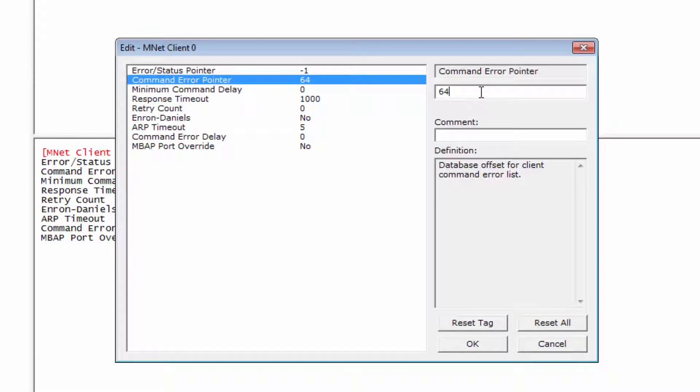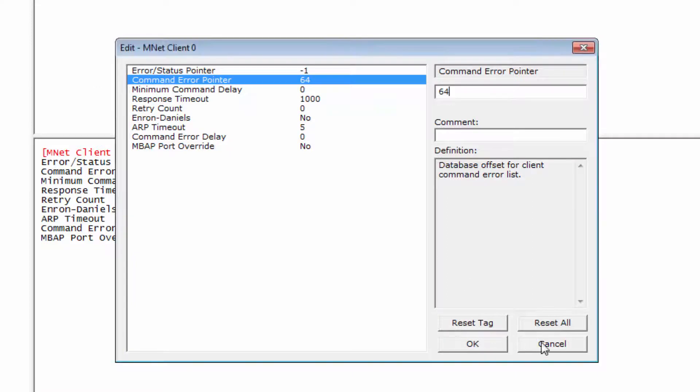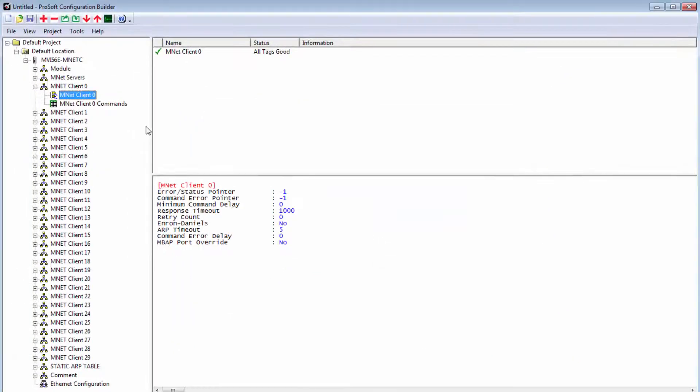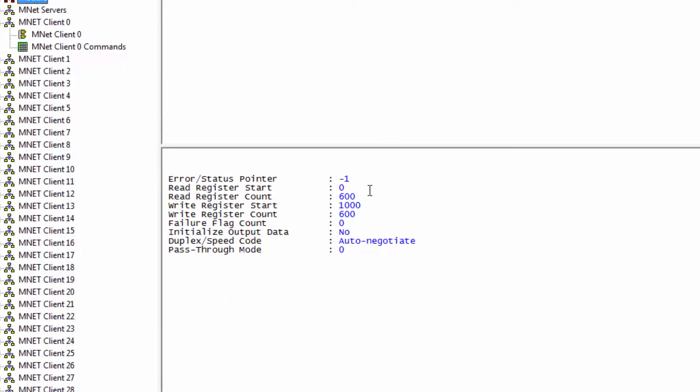Also, if you want the error code data to be accessible by the program, it must be placed within the Read Data section of your module. We recommend setting the Command Error Pointer towards the end of your Read Data section. So if I take a look at the module definition, my Read Data starts at address 0 and has a count of 600 registers.